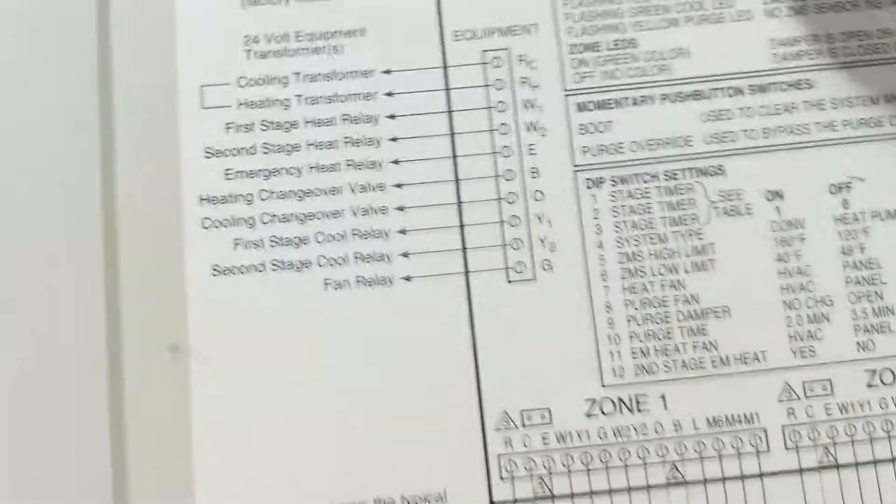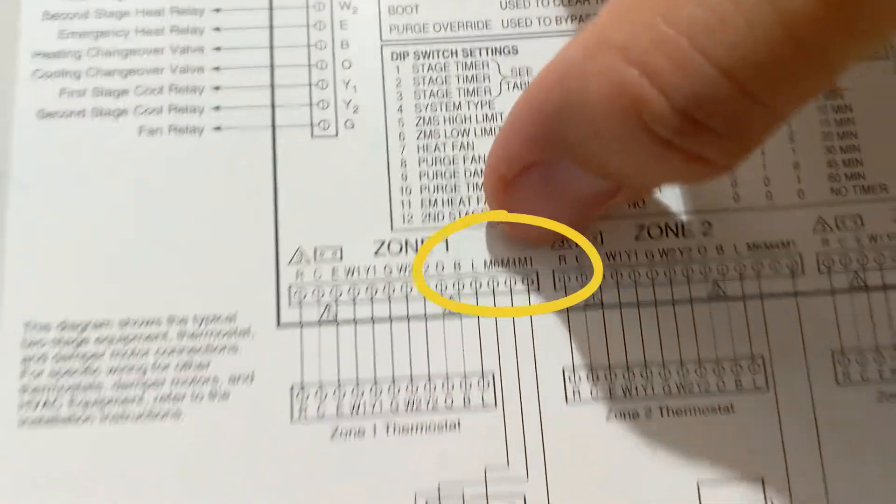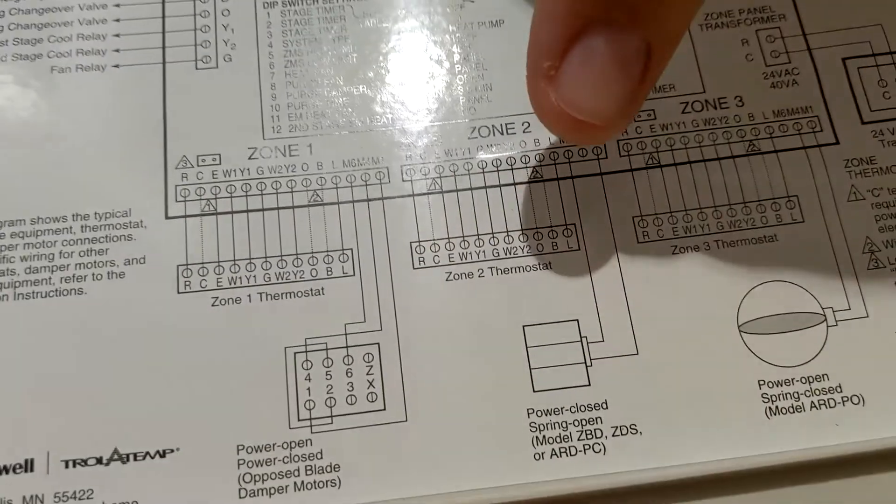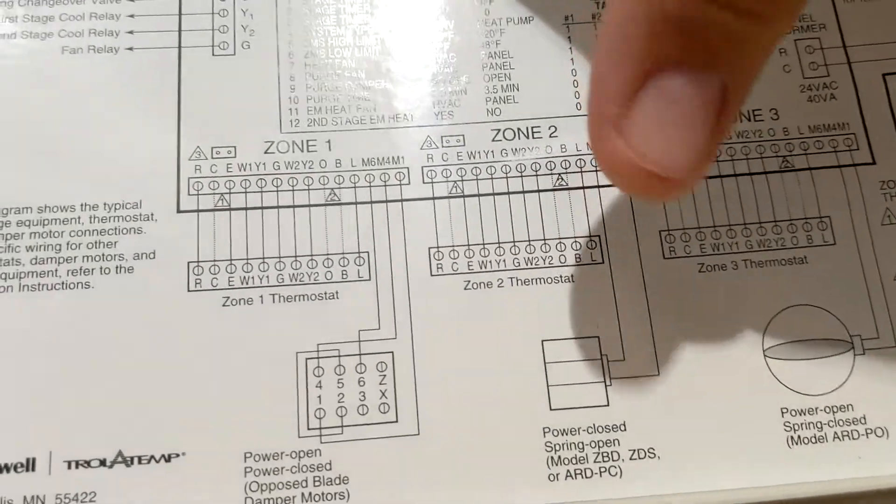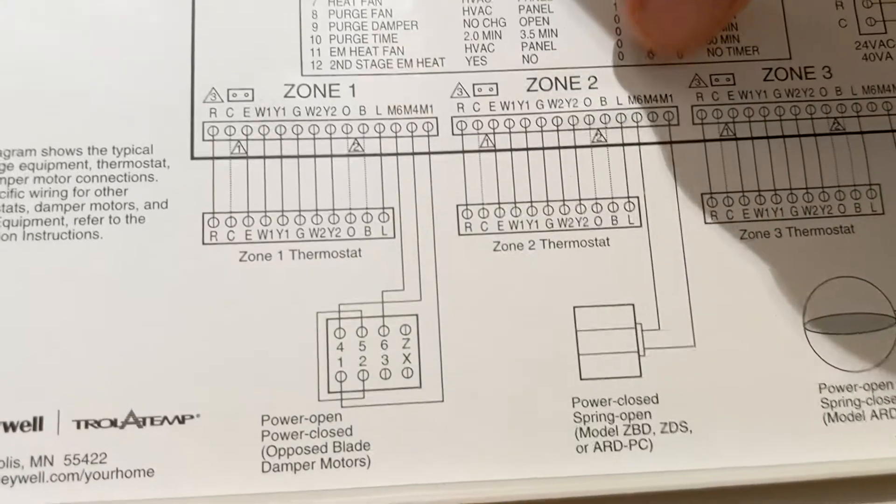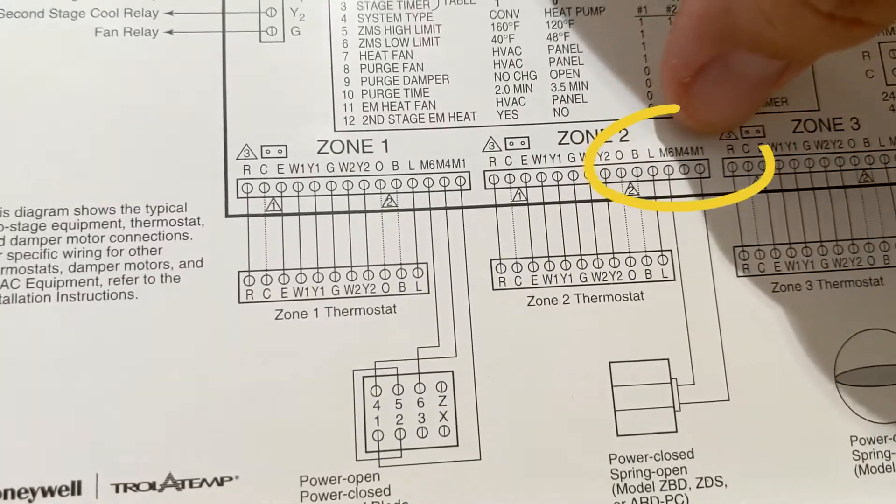M6 and M1, which is right here—M6 and M1 are the power for the damper. As soon as you take those out, the damper will open up, spring open. And then on zone two, M6 and M1, we...